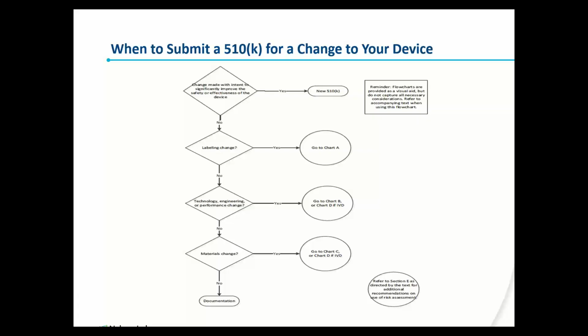However, and this is actually a true story, I have seen companies that have had over 1,200 changes to the device. And the question really becomes at that point, what point in the accumulation of those changes is the device no longer the original device? This is similar to the parable of Theseus' ship. For those familiar with this thought experiment, the real question is, if a seaworthy ship has all its parts replaced slowly over time, at what point is it no longer the original ship? Is it when the mast has been replaced, the planks, the outside of the ship? At what point do we draw that line and say, okay, the ship is a completely different ship than the original? These same principles apply to medical devices. And the question becomes, at what point is this a new device that could actually affect the safety and effectiveness? Unfortunately, with FDA, there is no hard and fast rule. So for you manufacturers, you're going to have to assess this on a case-by-case basis.